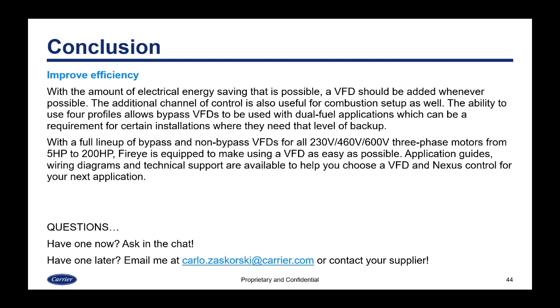In conclusion, VFDs should be added whenever possible to improve efficiency and electrical energy savings. The additional channel of control is also useful for combustion setup. The ability to use four profiles allows bypass VFDs to be used with dual-fuel applications, which can be a requirement for installations needing that level of backup. With a full line of bypass and non-bypass VFDs for 230, 460, and 600 volt applications and three-phase motors from 5 to 200 horsepower, Fireye is equipped to make using a VFD as easy as possible with application guides, wiring diagrams, and technical support. If you have any questions, please enter them in the chat. A link to the YouTube video version of this presentation will be sent out after the conclusion — thank you all for participating today.